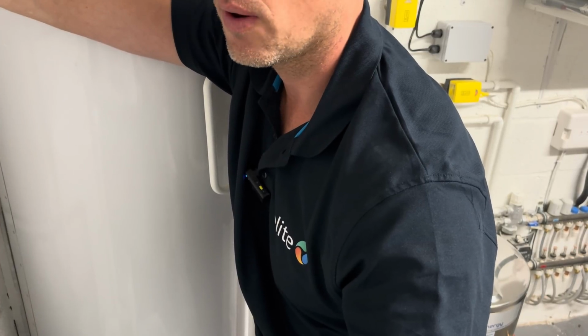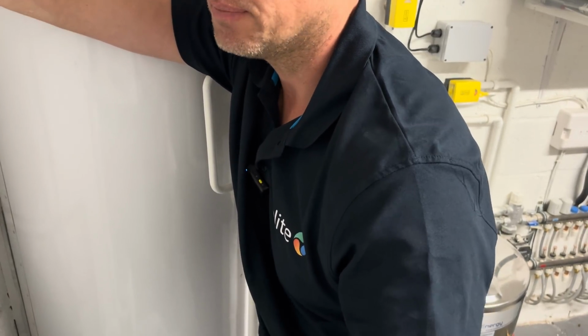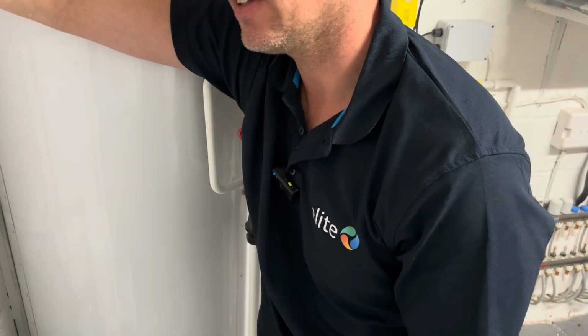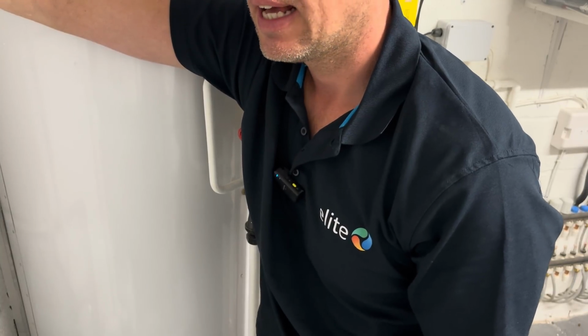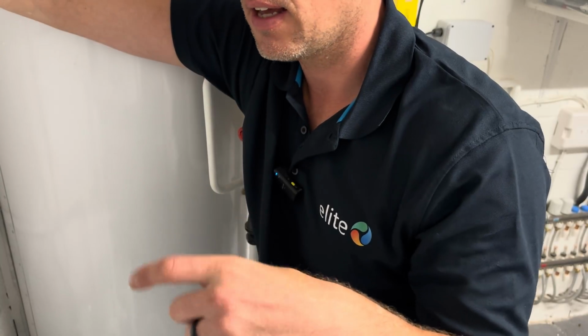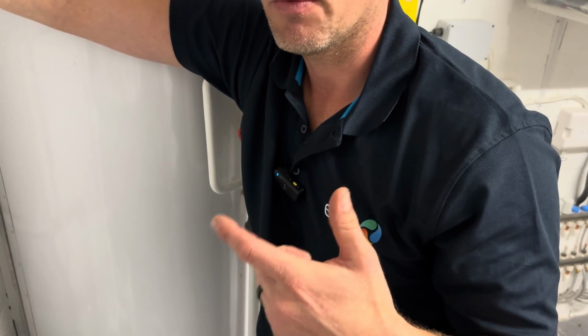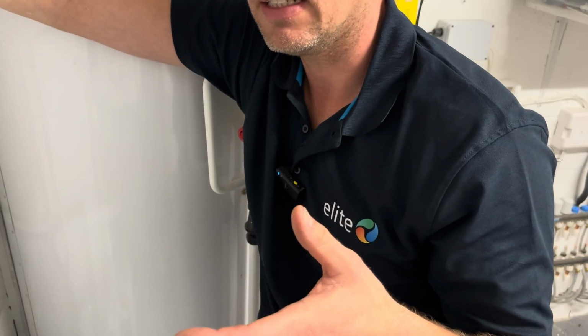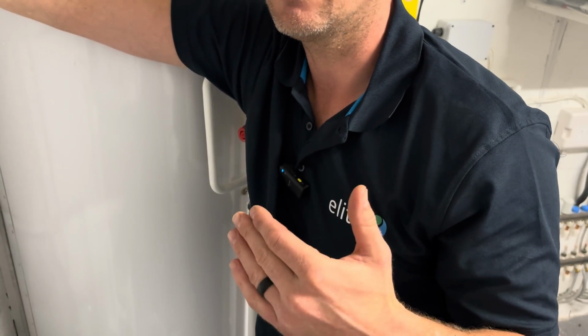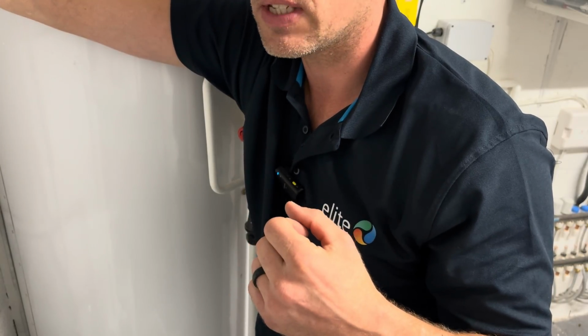So it's 14 kilowatt outside. I reckon this house is about 8 or 9 kilowatts at best. Can't really do much about that. It's not going to be massively problematic on the efficiencies. The heat pump modulates down to 30% of its capacity, so it's just going to start cycling a little bit quicker in them warmer temperatures, 12, 13 degrees, whereas the right size heat pump would not cycle as much throughout the year. So that's what comes with an oversized heat pump.